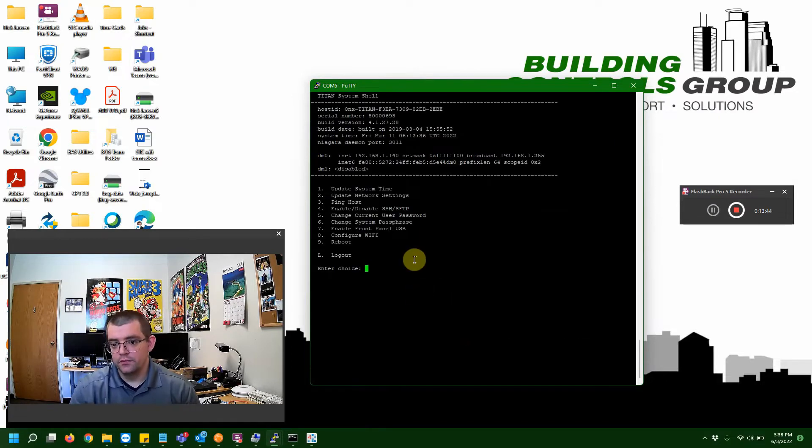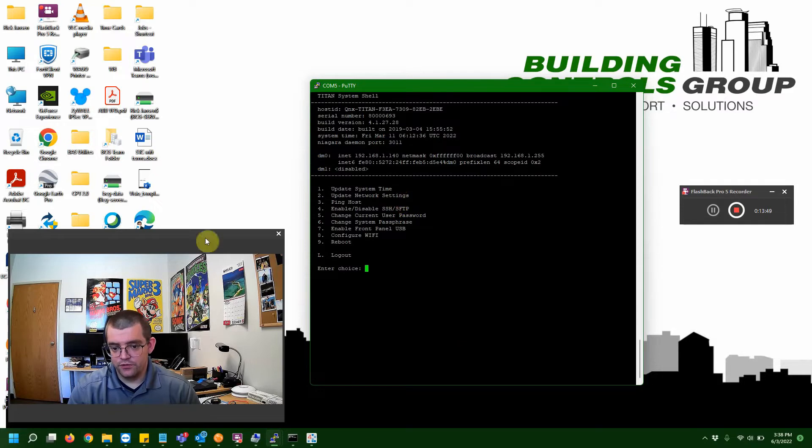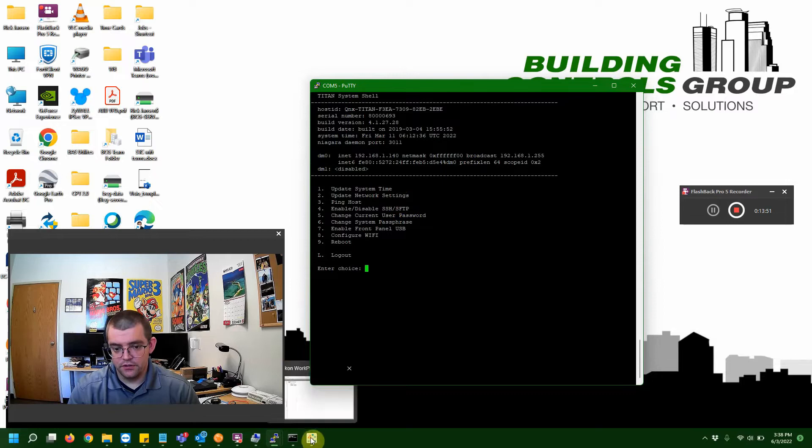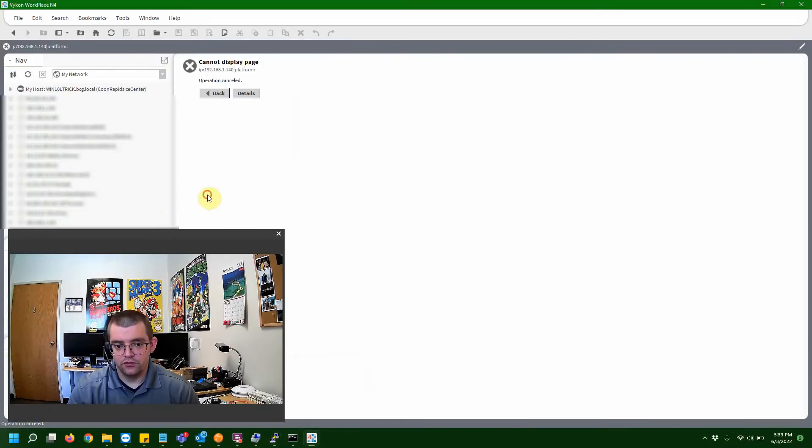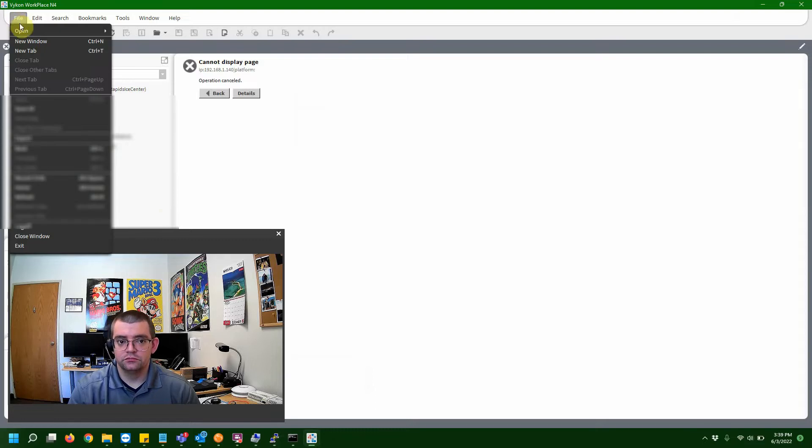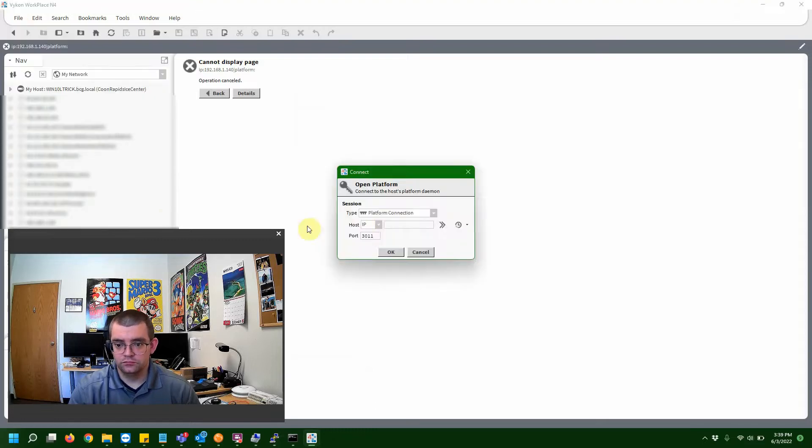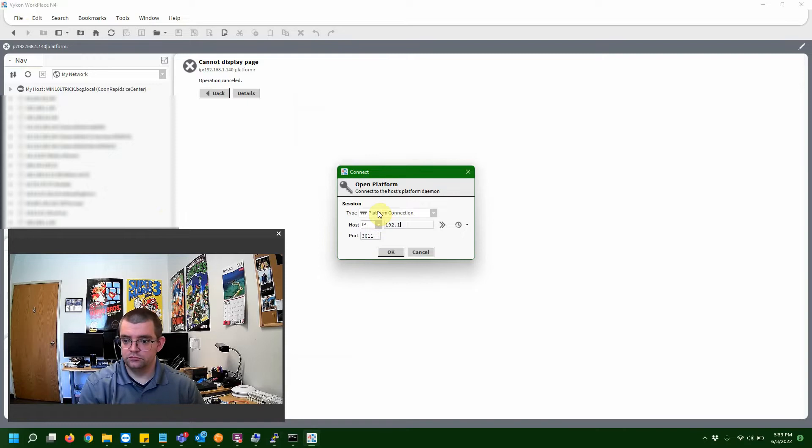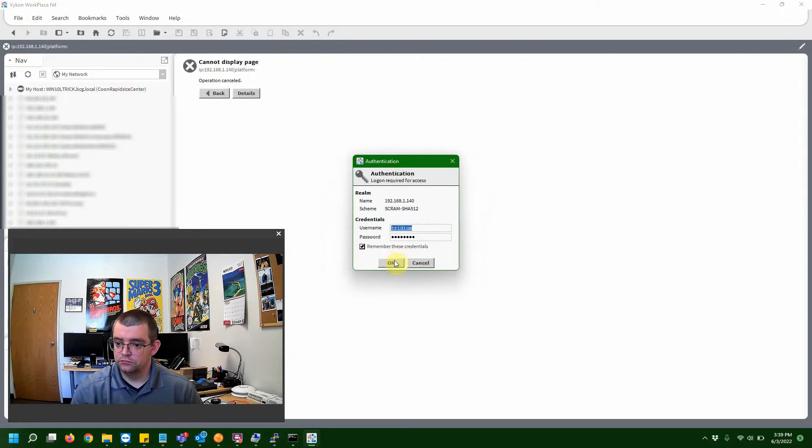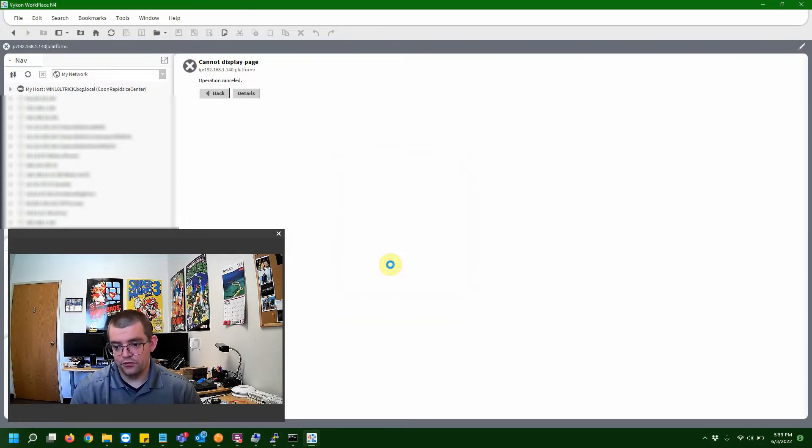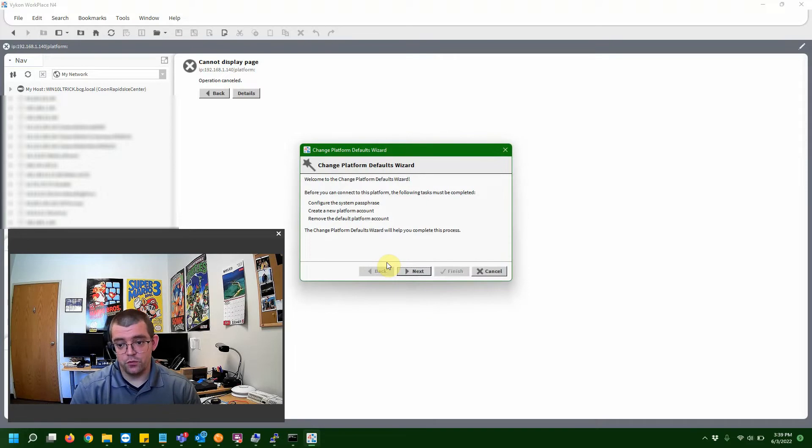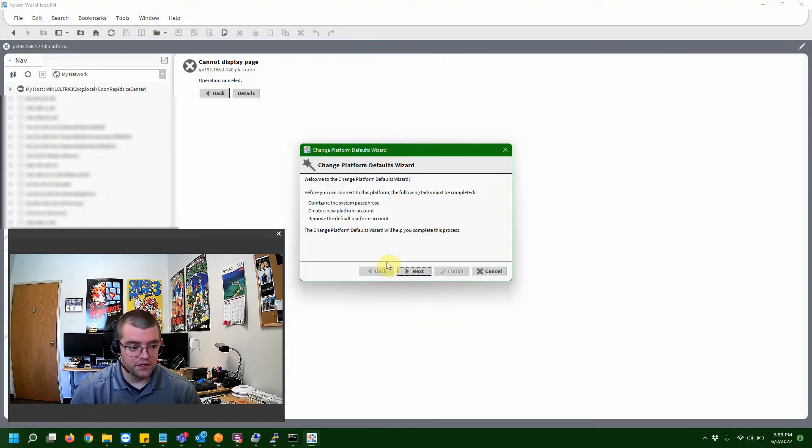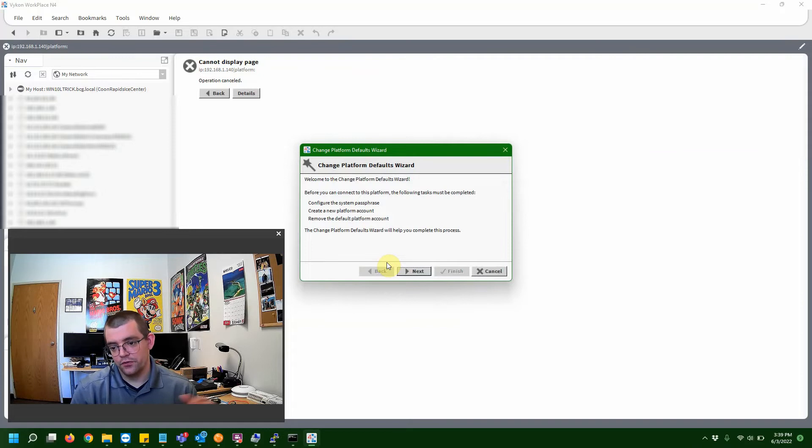All right. So, we're logged in. Things are looking good. We haven't seen any errors that would stop this station from starting up. So, let's go ahead and launch Workbench, and we're just going to go ahead and see if we can connect to this Jace. And, I already have my credentials in there, so we're good. And, if we've gotten to this screen, we're good. This means that this Jace has been successfully wiped back to factory credentials. This would be basically the exact same thing as pulling this thing brand new out of the box. And, you can go ahead and do your commissioning, put your station back on, or whatever it is you intend on doing here going forward.